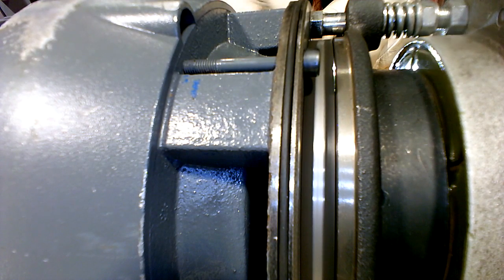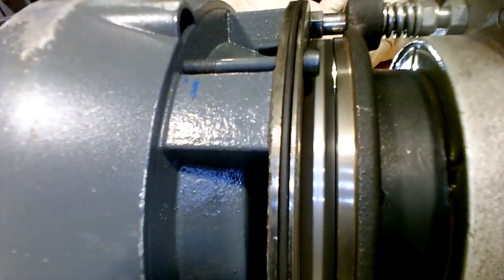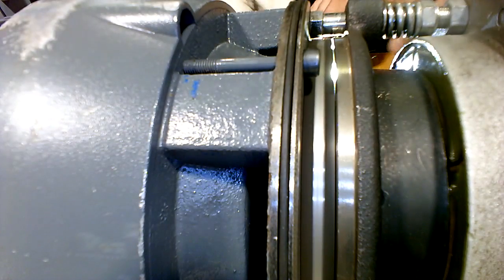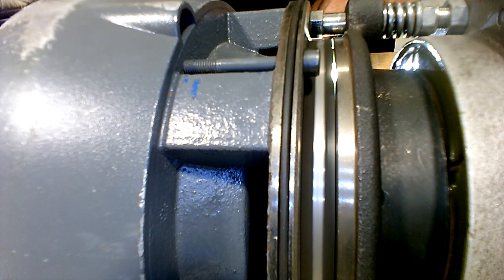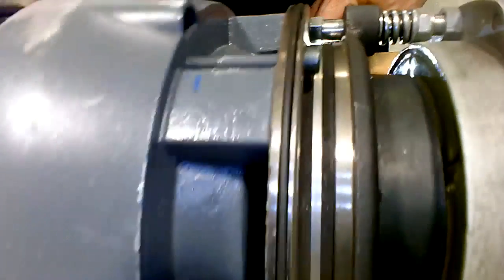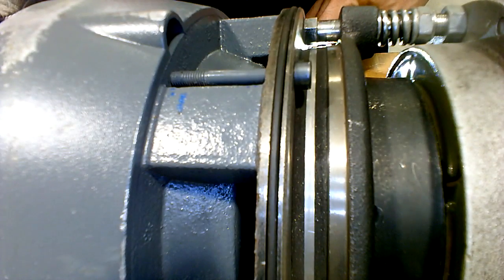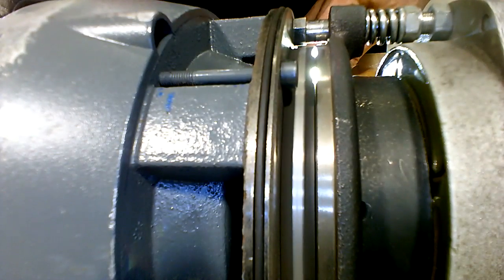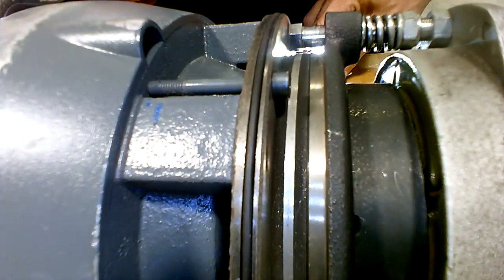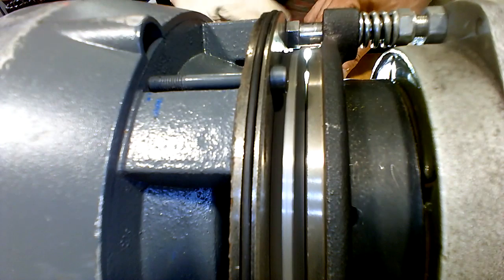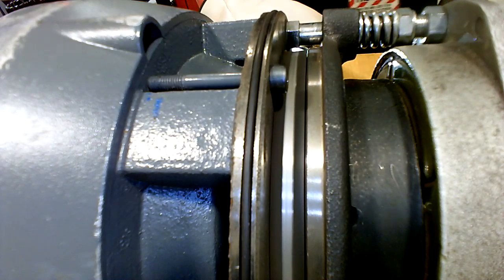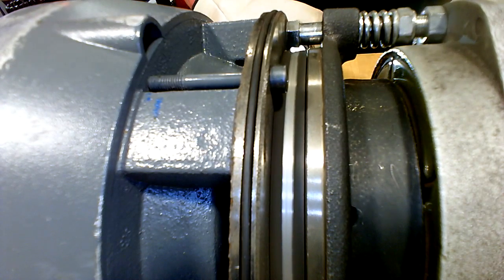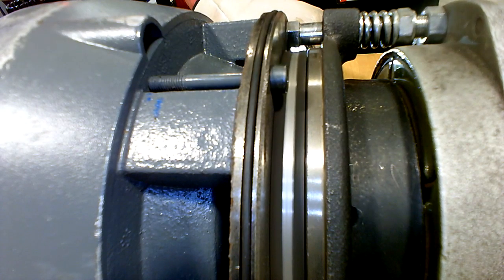Somebody help us right at that angle. We don't get too close now. If you see the gap in there, now watch that gap close when I de-energize it. See it close? Now the gap's going to reopen. See the gap in there? You see some daylight, and now you don't. Man, that closed up. That little bit of a 10 thousandths gap in there is what the manufacturer says it's supposed to have, to give it free motion and not drag.